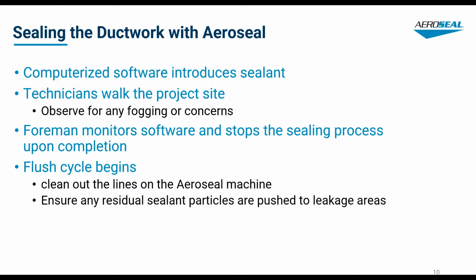During the seal process, while the technicians are walking around, the foreman monitors the software and stops the sealing process upon completion. Then the flush cycle begins. After the seal is complete, they need to flush out any residual sealant in the system, which isn't very much at all. There are a couple quarter-inch tubes pumping the sealant for us, so there's not much left in there. It's kind of like a final push for us as well, because all of that sealant still goes into the ductwork and is still doing what it's supposed to do. We're just bringing it down a little bit tighter during this process.